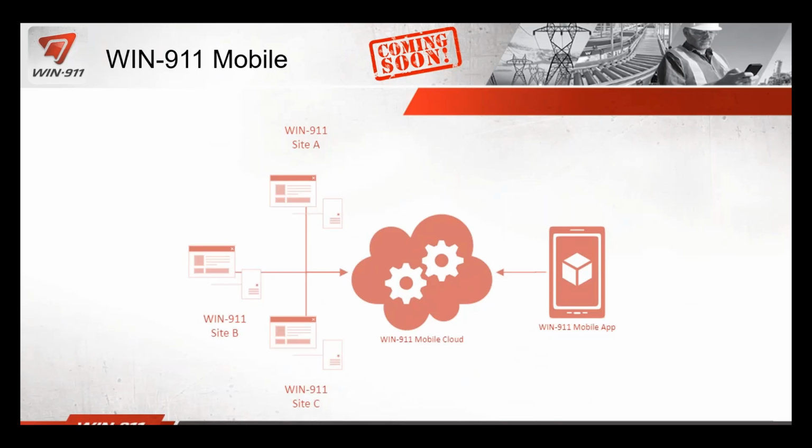Sure. So we've moved from a device-centric approach to a user-centric approach. Instead of an individual phone or an individual tablet being a connection, we're now login based. And so users can switch seamlessly between a tablet and a phone that they have the same login for. Those devices are connected up to the Win911 mobile cloud, which sits offsite up in the cloud. But all of the information is still coming from the Win911 side on premise. So all of that chat history, all of that logging is actually over in the Win911 and in that SQL server. All of the alarm details are there.